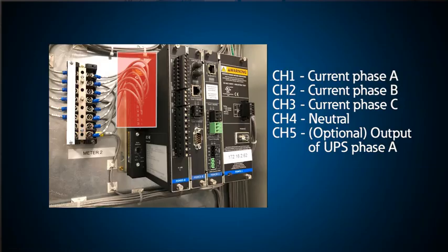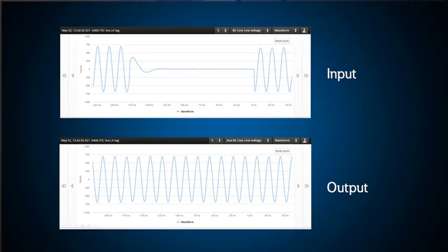Additionally, with five current channels standard on the PX meters, we have the ability to see all three phases of input current and at least one phase of output current using the neutral or ground channel to monitor that output current. This gives us a very precise picture of exactly how quickly we can detect and respond to an incoming power anomaly, but also provides the actual transition waveforms so the viewer can confirm that in a UPS application, the output voltage and current are undisturbed during a significant utility power event.